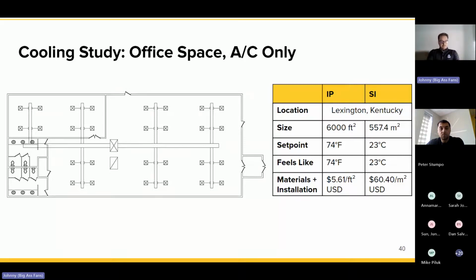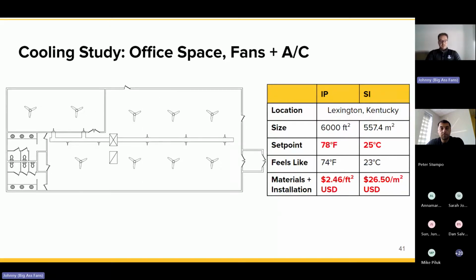So this is a conventional office space where you would have a drop ceiling, these square diffusers throughout. Again, those branches of ductwork that we often see. Set point a little bit higher, 23 degrees, and just note the materials and install costs. Now, when we add a fan or fans to this environment, you can see we're sticking to one simple ductwork down the middle with sidewall diffusers that are going to blow into the space and the fans are going to mix. Okay, so we've raised the set point again a couple degrees, saving that electricity, keeping people comfortable.